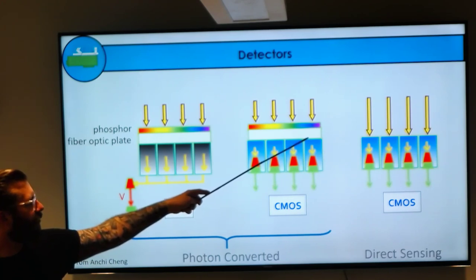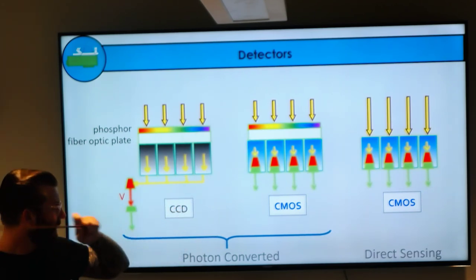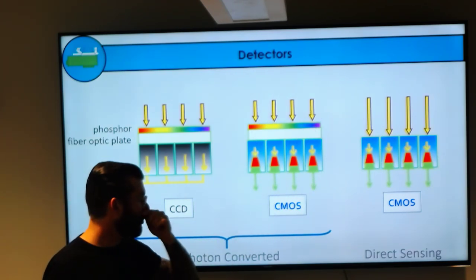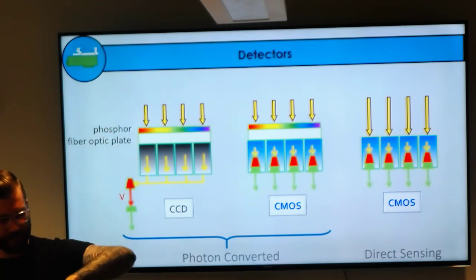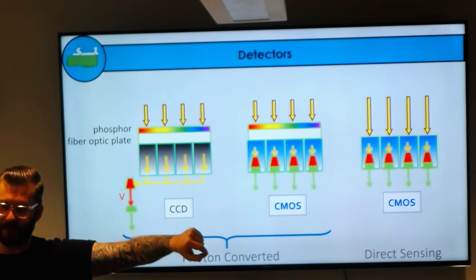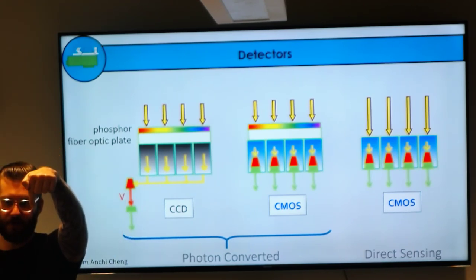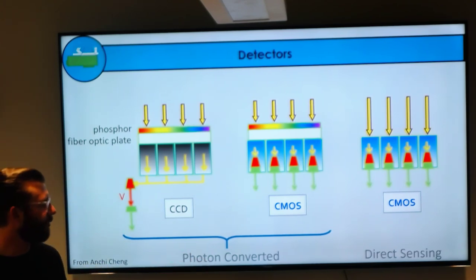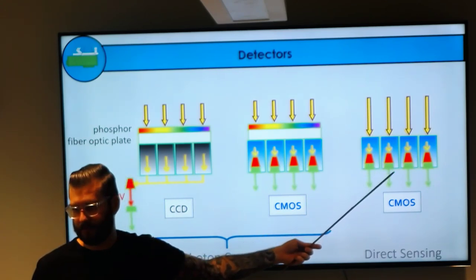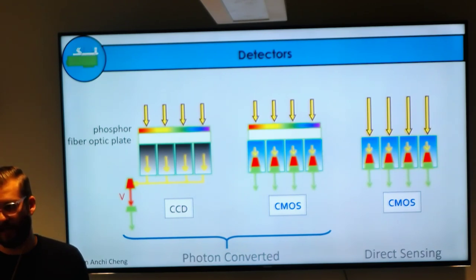The other type are direct sensing CMOS detectors—these remove the need for a scintillator and instead detect the electrons themselves, which reduces noise from the detector. When an electron hits a scintillator it scatters in different directions, kicking off photons at each change of direction, causing blurring of the image. Moving to direct sensing reduces that noise. These detectors are also much faster since we no longer wait for scintillation. So we now have much faster detectors with far less noise—probably one of the major engineering accomplishments enabling the resolution revolution.